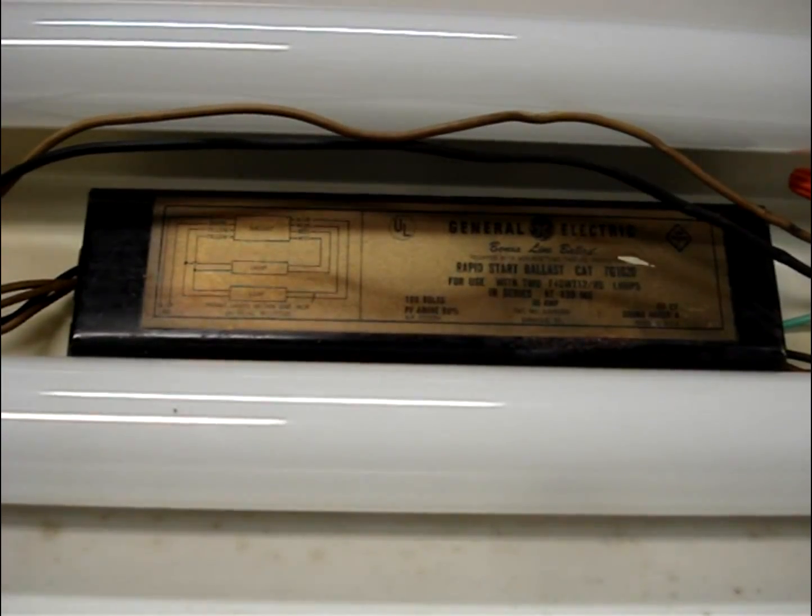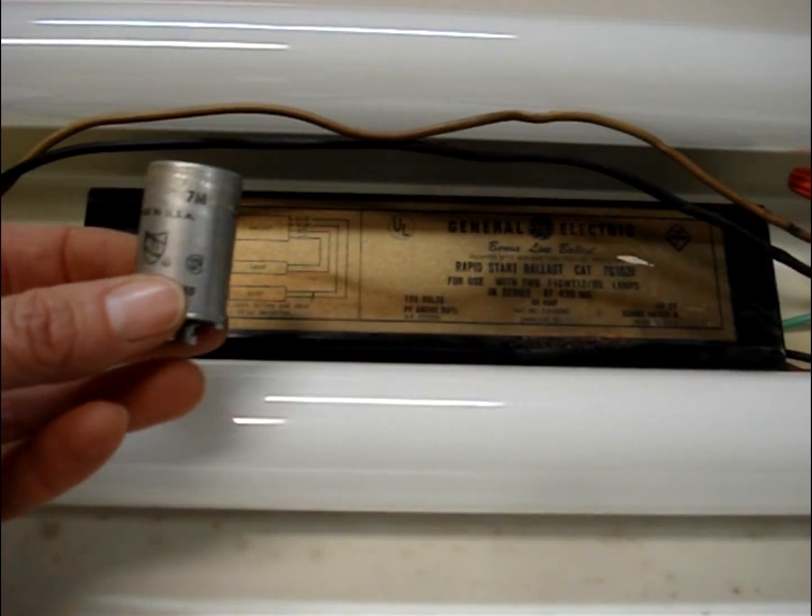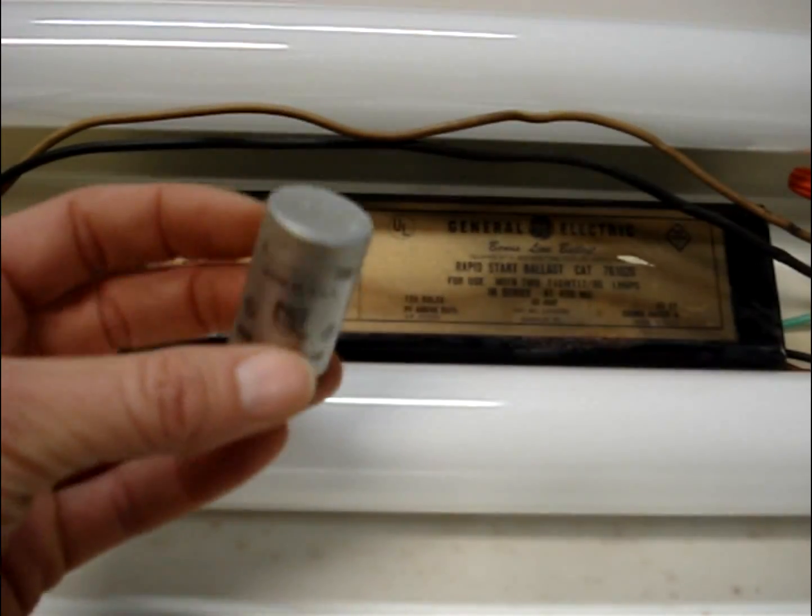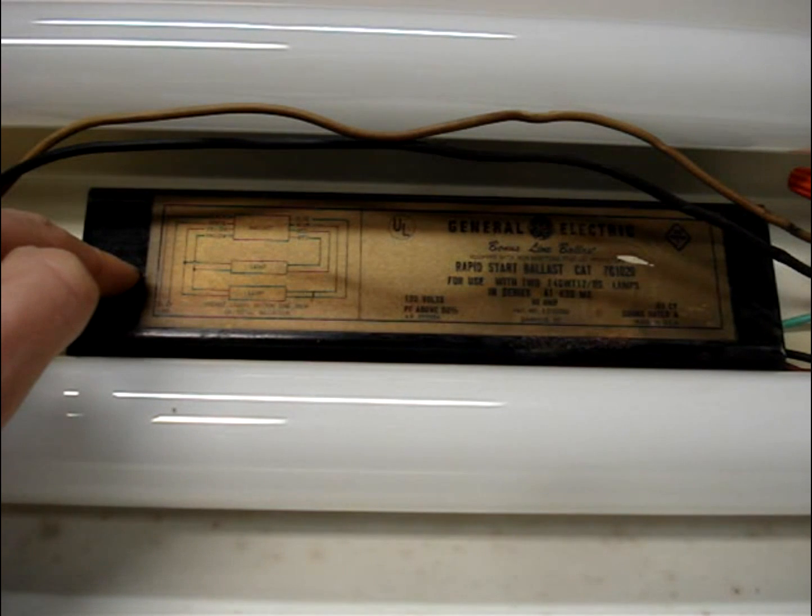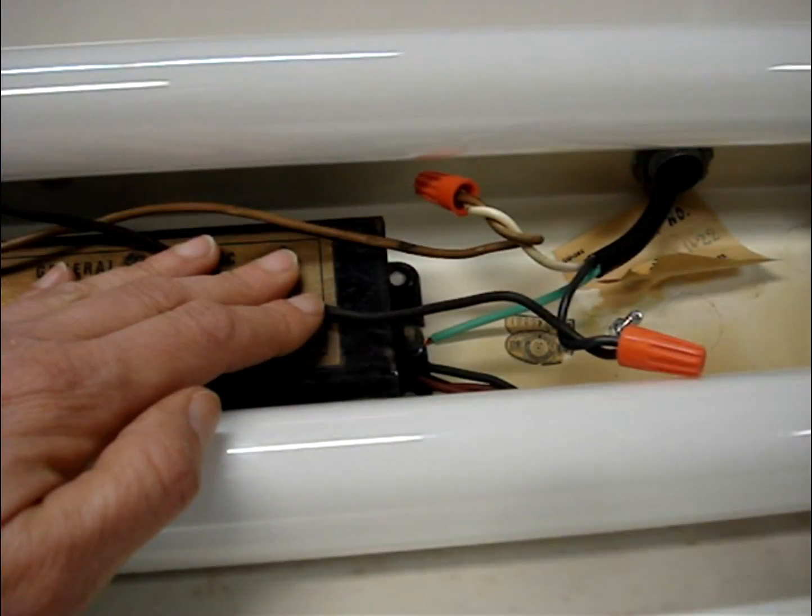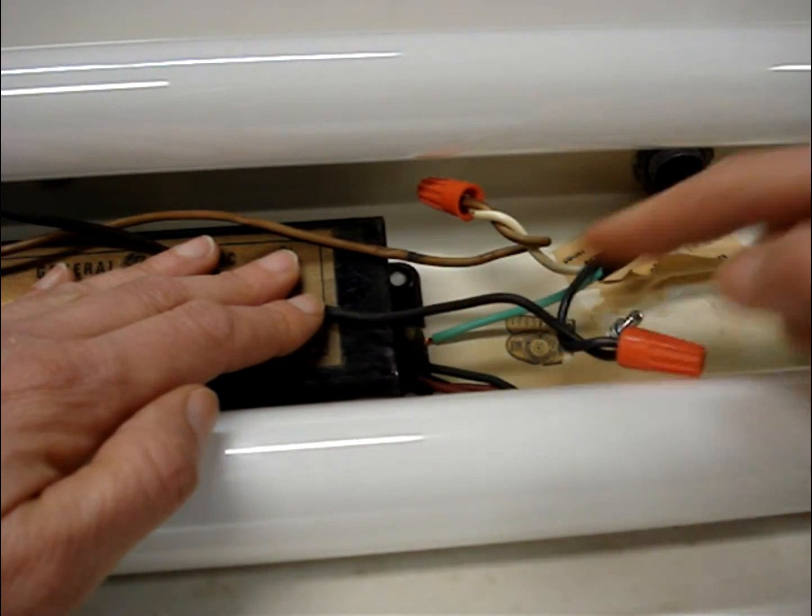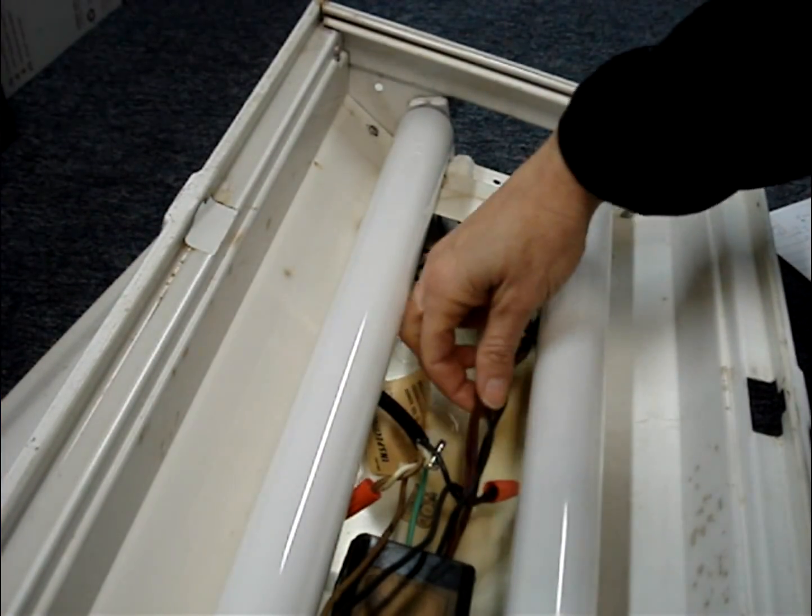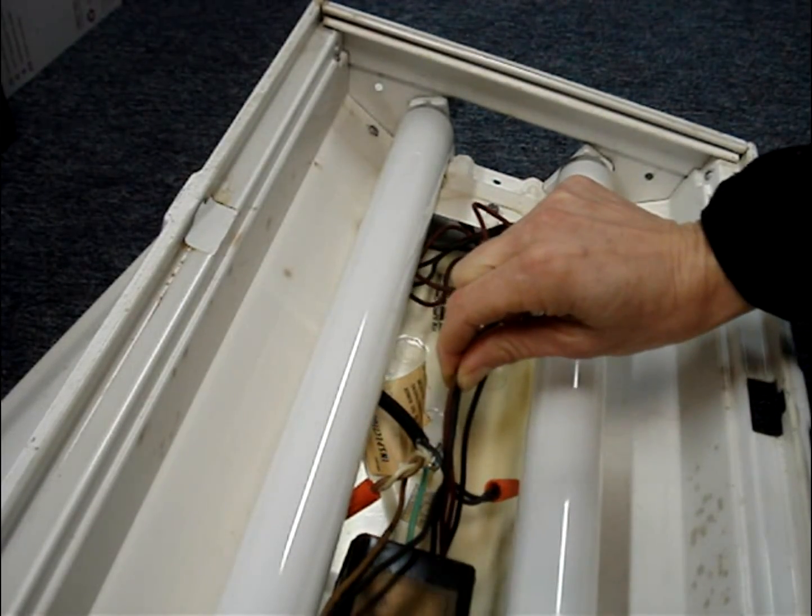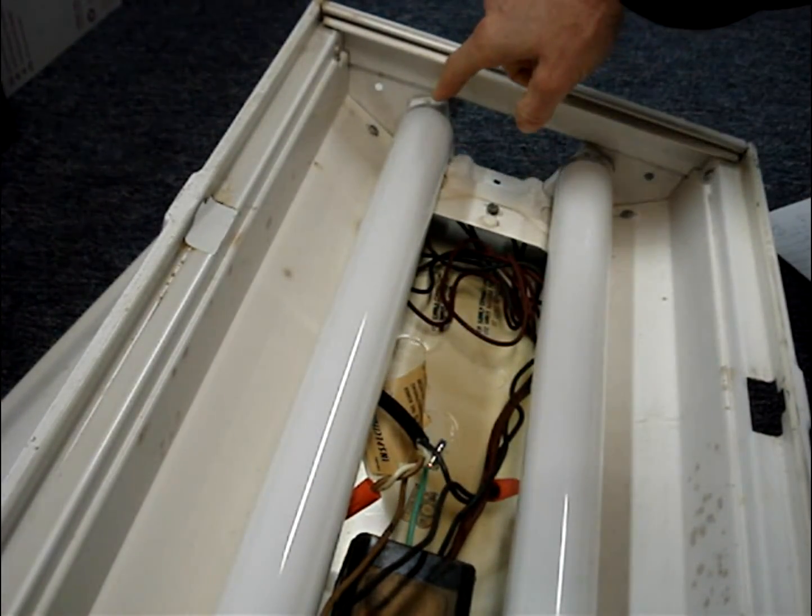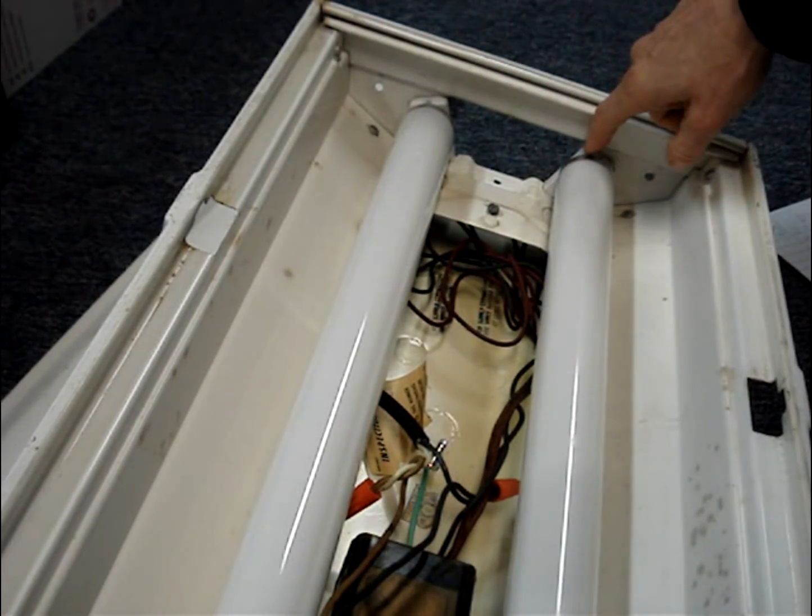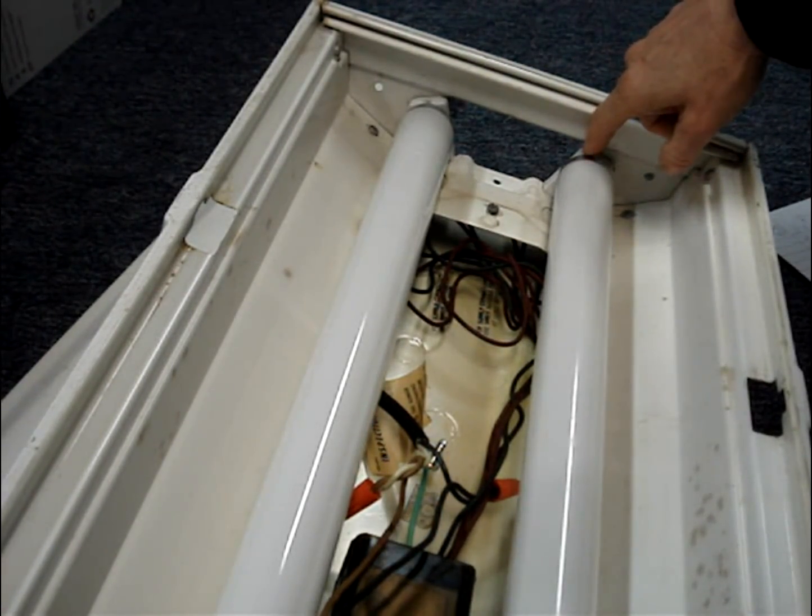Inside of a fluorescent tube fixture, you'll find a ballast and in some older fixtures you'll find a starter and a ballast. Both combinations have the same end result, they just accomplish it a little differently. 120 volts AC feeds into the ballast. The output from the ballast is connected to the sockets on the fixture and the sockets are sometimes called tombstones.